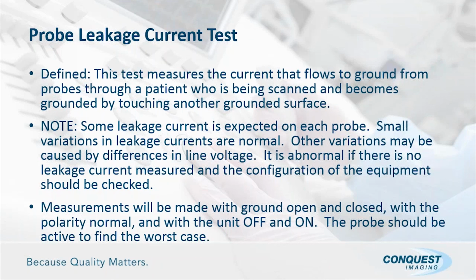And the probe should be active to find the worst case. You want to be actively scanning with a probe, and you want to be testing it in the multiple modes, B mode, M mode, color Doppler, whatever you're checking. You want to find the worst case.